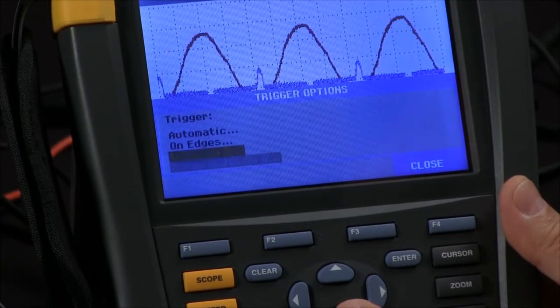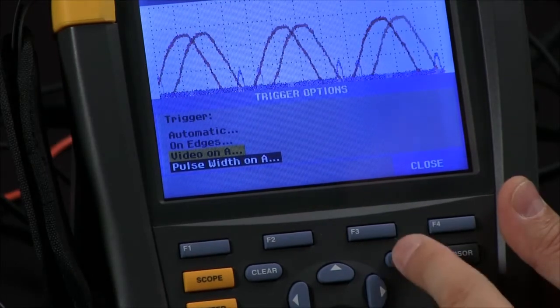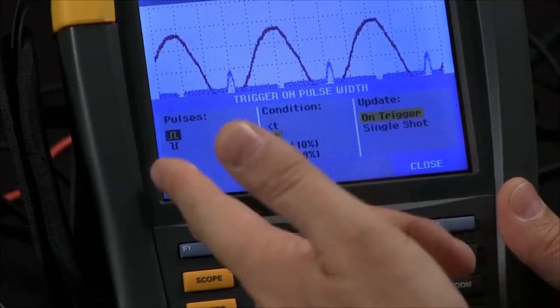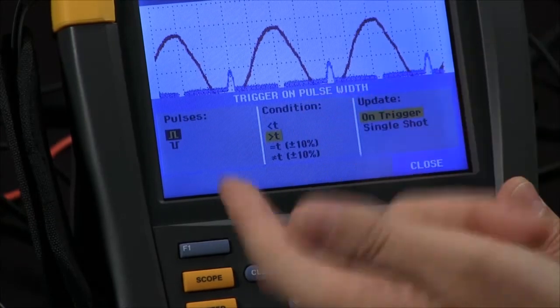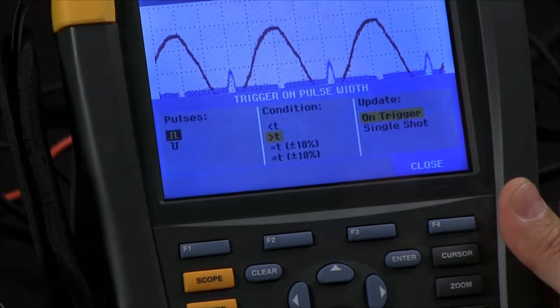We can also go back, say if you're looking at the output of a drive, and now you can trigger on a pulse. By selecting that, you can select your positive or negative pulse, the transition time, the pulse width, enabling you to get the best display on your scope meter at all times.